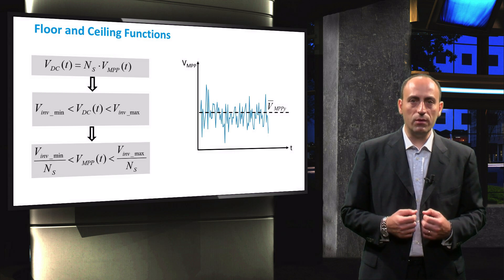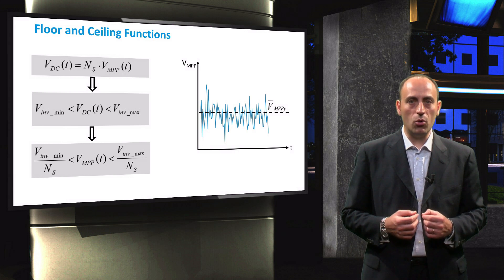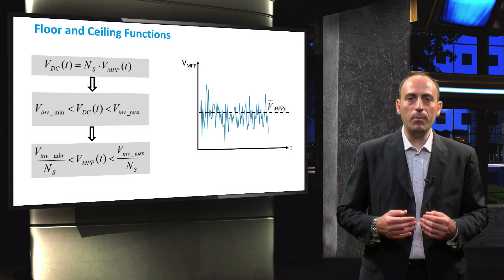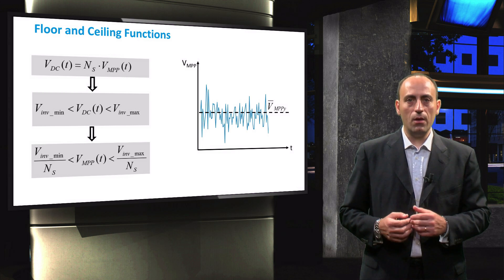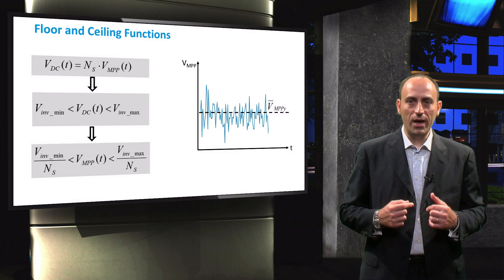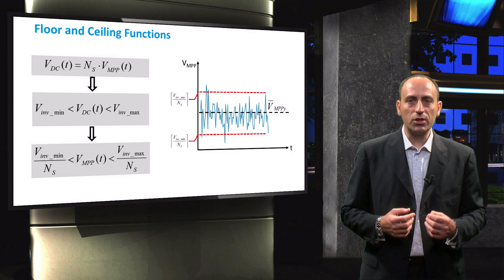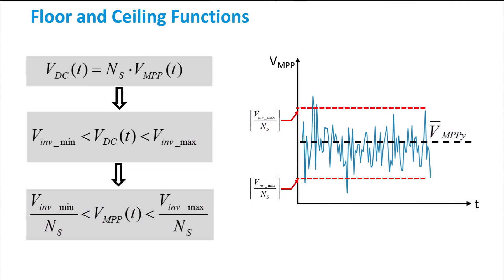By rearranging the terms, the voltage limits of an inverter for a single PV module are related to VMPP and the number of series-connected modules according to the shown equation. Now, if you round up the value of NS, a fraction of the peak voltages in the shown VMPP curves gets cut off. This consequently leads to a small voltage loss and a loss in the output power. In order to minimize this loss, the number of series-connected modules gets rounded down to the nearest integer.